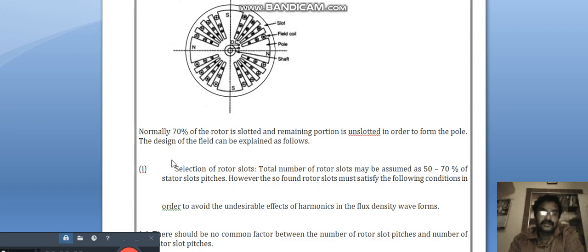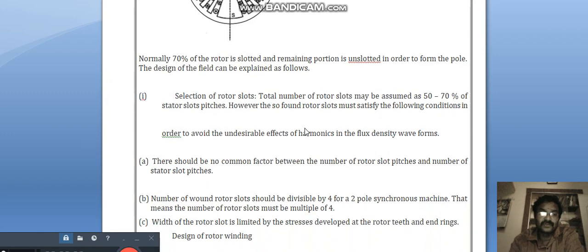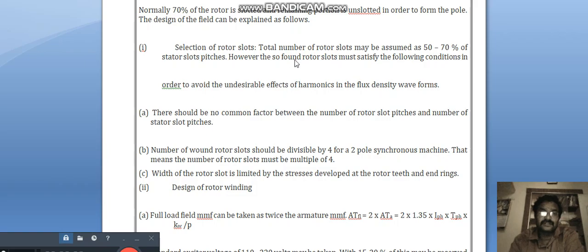The design of the field can be explained as follows. Selection of rotor slot: total number of rotor slots may be assumed as 50 to 70% of stator slots. However, rotor slots must satisfy the following conditions in order to avoid the undesirable effect of harmonics in the flux density waveforms.